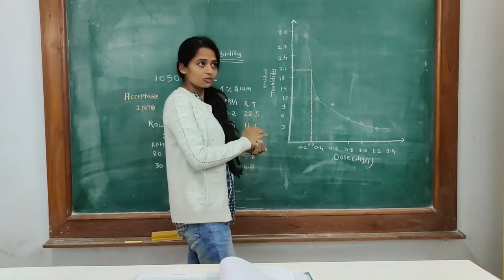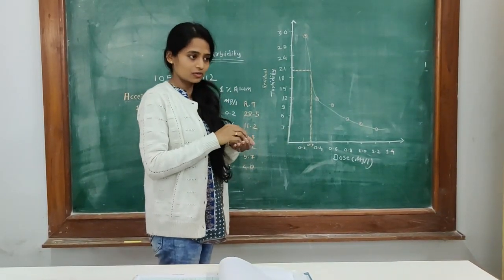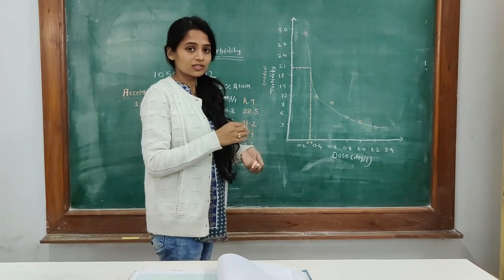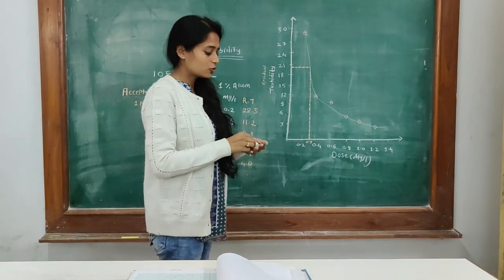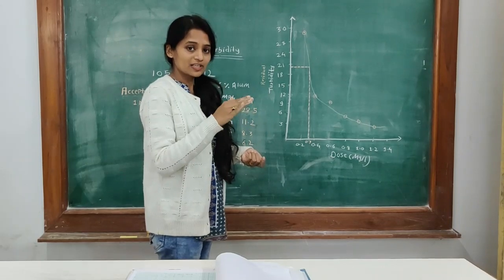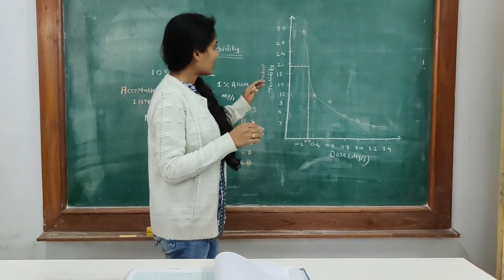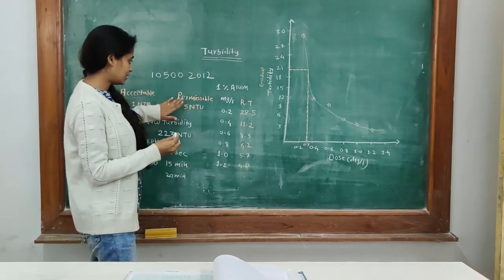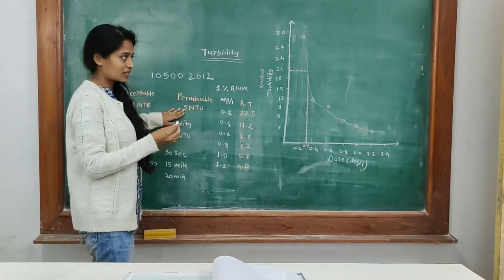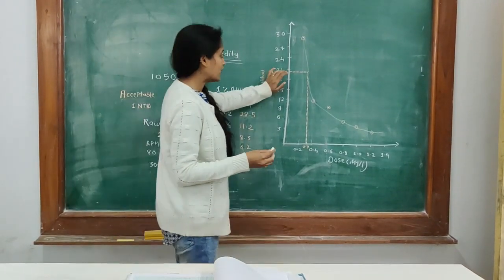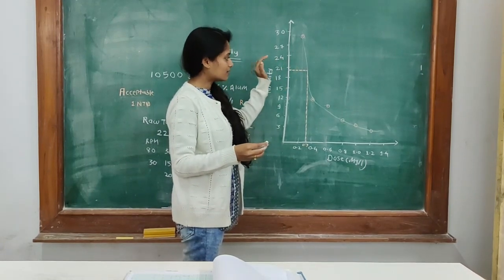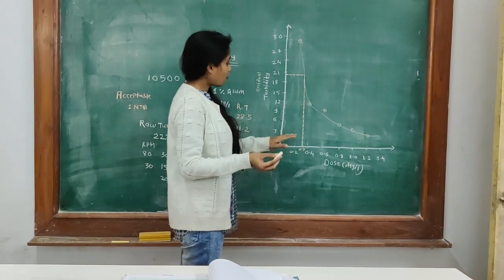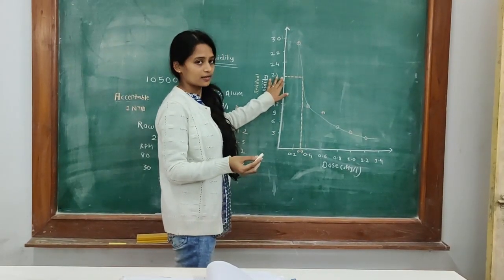Because you might have learned in your water treatment processes, just go and read once, that during those processes like sedimentation and then filtration, the turbidity gets reduced to these limits. So why should we go for extra limits? If we are getting 20 NTU here, then that turbidity will be further reduced in those steps. So for optimum coagulant dose, 20 NTU is taken as standard.